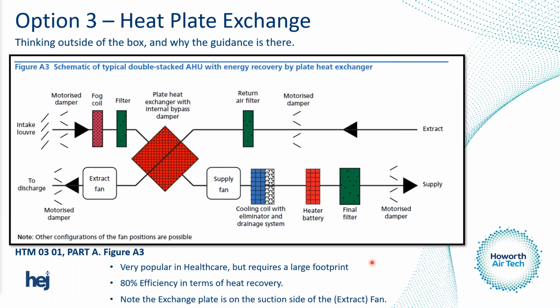Option 3 is the heat plate exchanger. This is probably one of the most common air handling units within healthcare. Again, you can see the components are at low level. The cooling coil is on the discharge side of the fan as the air moves in this direction. We have circa 80% efficiency from the heat recovery in these. Obviously, we need to make sure that this is a fog, not frost, and that's 2K to the outside to increase the efficiency from the heat plate exchanger.